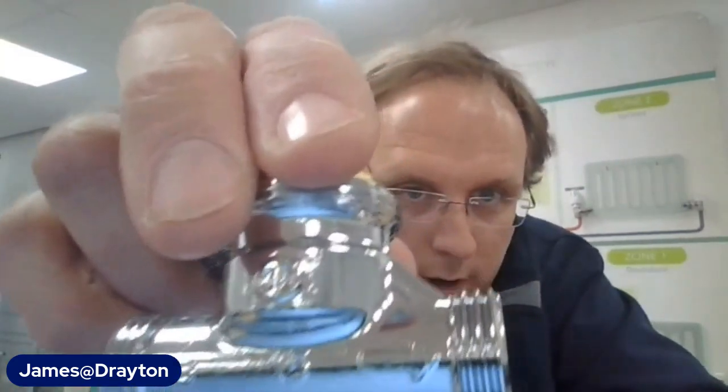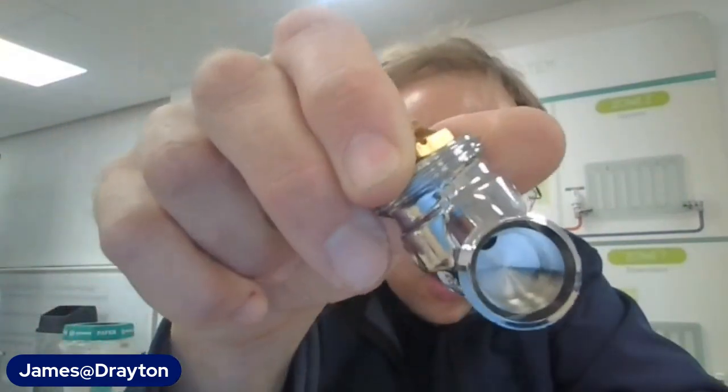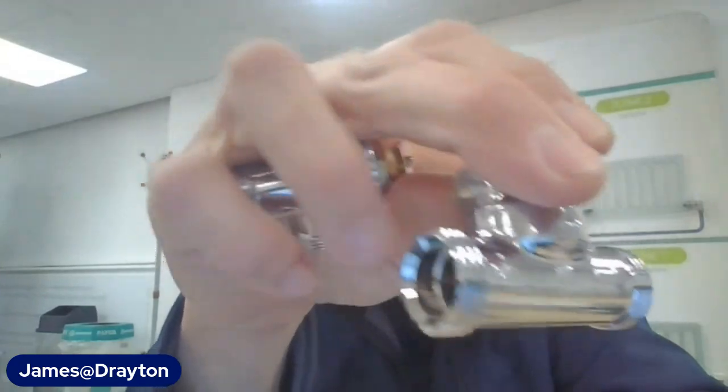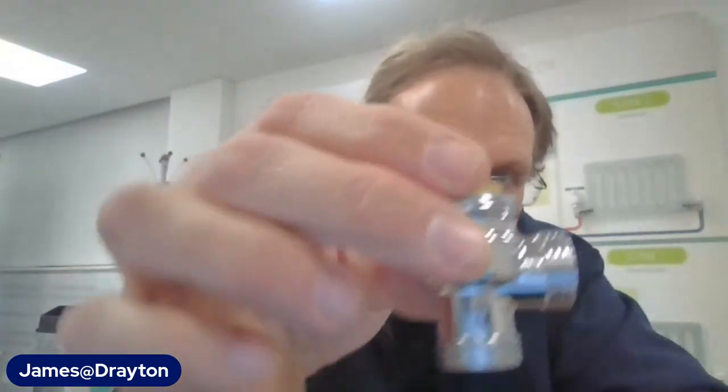It's exactly the same on the straight. I mean, the Drayton straight valves have always been unidirectional, and that's really just because of the way that they're constructed. You can see that the ports at either end are completely different. But with angled, a 15mm angled always used to be bidirectional. These aren't. So you can't just blindly go in and retrofit to radiators and replace like for like, without doing some measurement of which is your flow and which is your return.